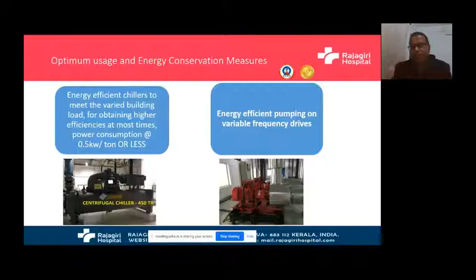Now, we did speak about air conditioning—it is a major power consumption for a hospital. The air conditioning plant has to be designed and selected for very high efficiency, as low as 0.5 kilowatt per ton. For example, the water-cooled centrifugal chillers we have in the hospital run at very low power consumption, as close as 0.5—meaning it takes only 0.5 kilowatt to give you 1 ton of air conditioning.